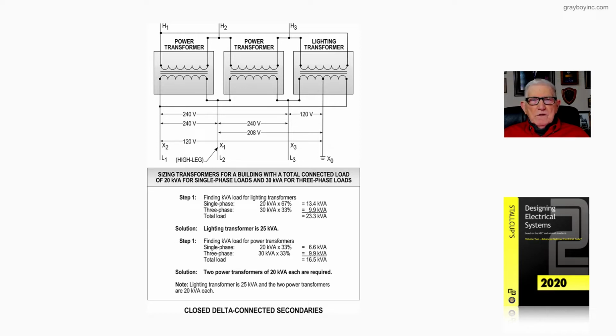Now we need to close end 2 of the delta. So we take the inside winding, which is the right side of power transformer winding number 1, and connect it to the winding of power transformer number 2, and that closes one end of the delta. Now to close the delta winding completely, we go to power transformer 2, and that winding connects to the lighting power winding, and that closes the delta.